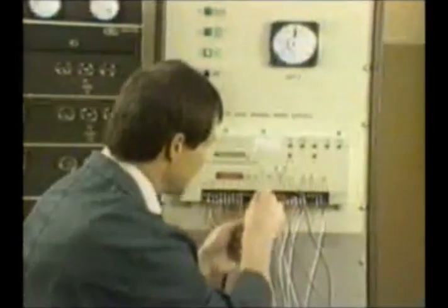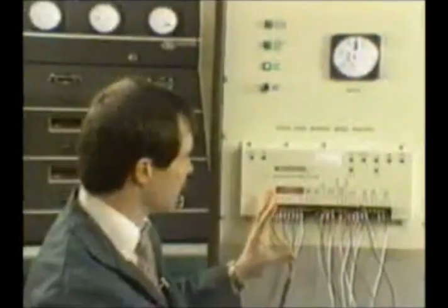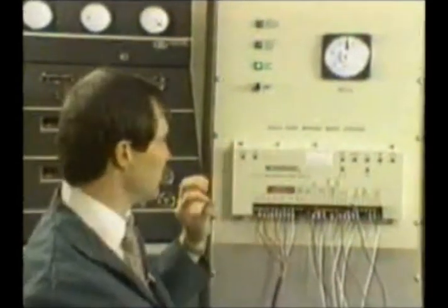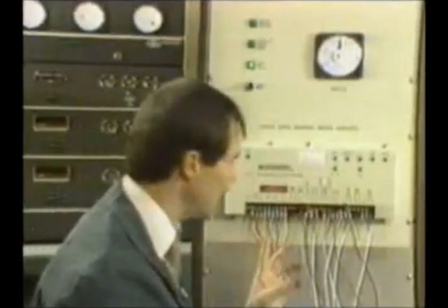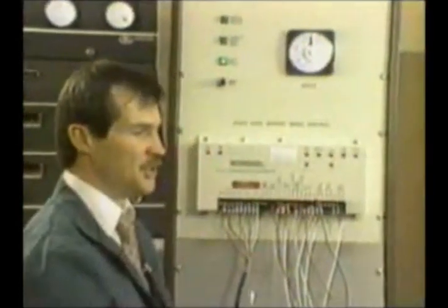I'm going to use my digital meter, hook up to terminal 12 is minus, 13 is plus. Droop pot is set at 0, so we'll be running at 0% droop or isochronous. That's what we've been running at so far. Now I'm going to put on 50% load on the engine. I'll put on 33%. So now on the engine we're carrying 50 kW, which is a third of rated. I want to make sure that once I get up to 100% load, I'm reading 6 volts at my load gain. My load gain is set at mid-range.